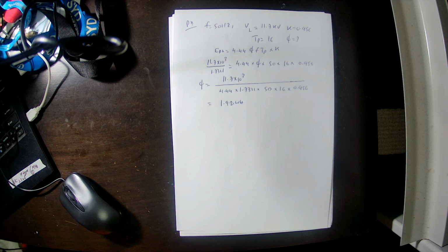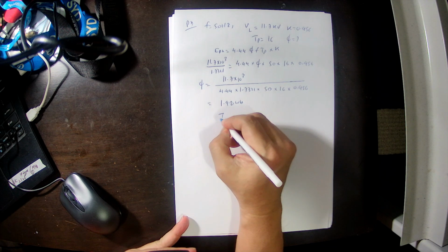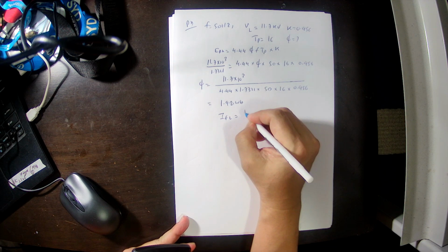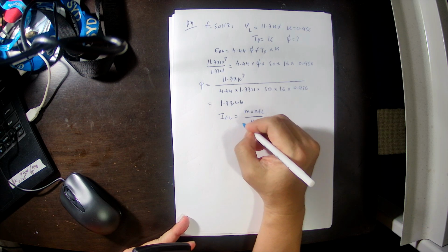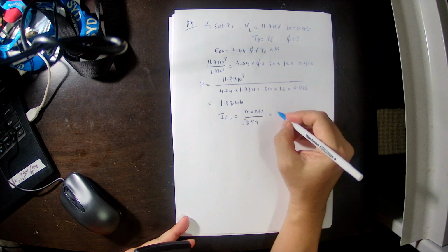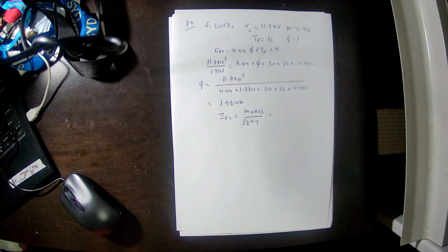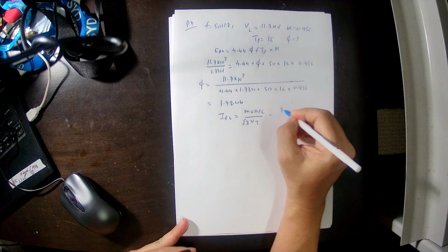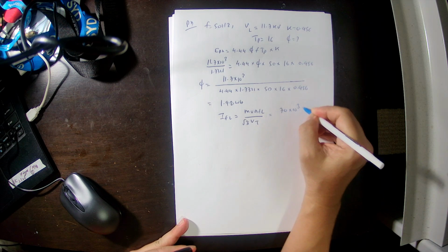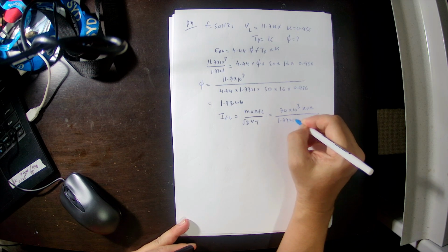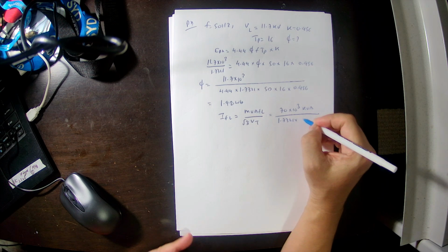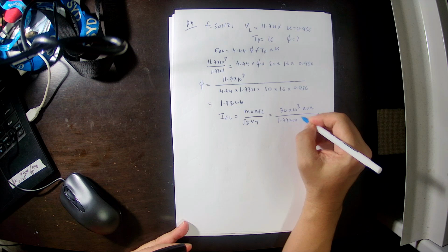We also need to calculate the full load current rating. So this is IFL, which is MVA FL divided by root 3 VT. Now we have the terminal voltage 11.7 kilovolt. So 70 MVA, or 70 into 10 power 3 kVA, divided by 1.7321 and the terminal voltage 11.7.